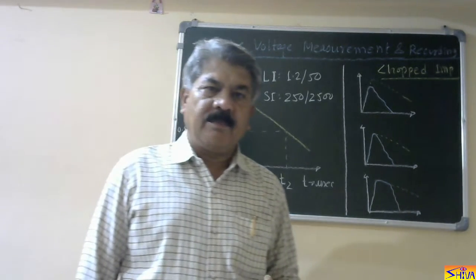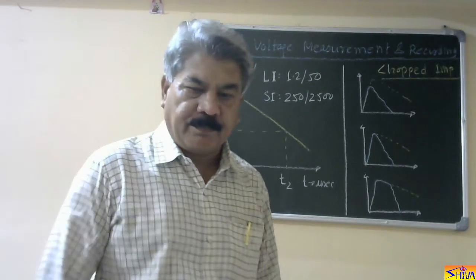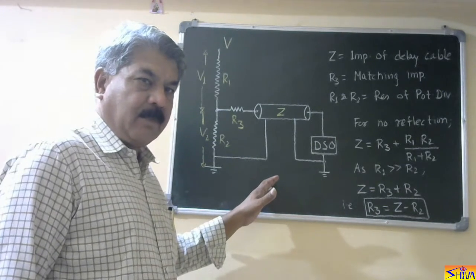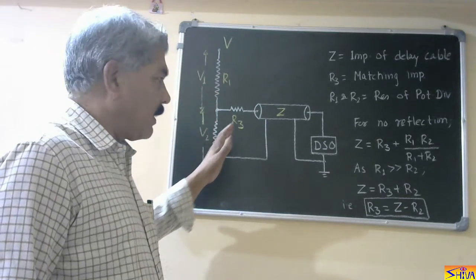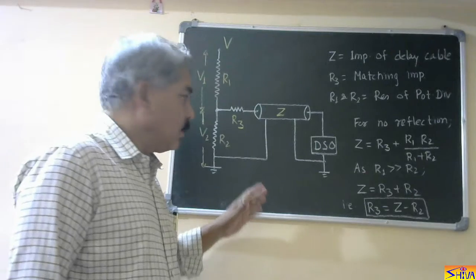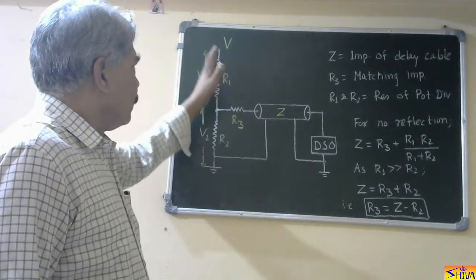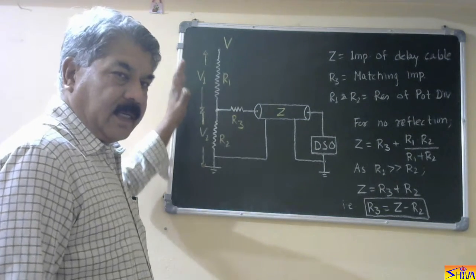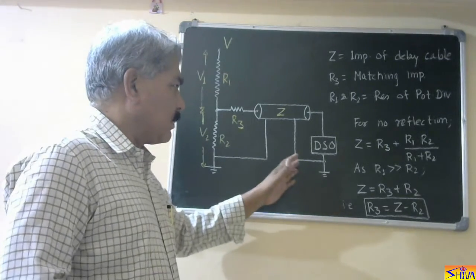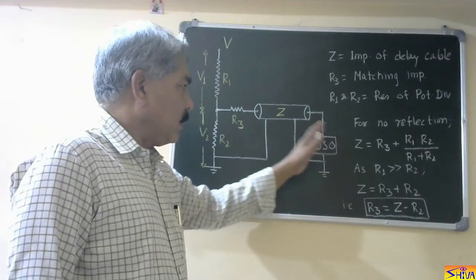So, that recording is done by potential divider plus digital storage oscilloscope. That I will explain now. This is the arrangement for impulse voltage measurement and recording. I have shown here a resistance potential divider, and for recording, a digital storage oscilloscope is there. We can use a capacitance potential divider also. The high voltage transformer, that is the impulse generator, test object, and this resistance potential divider, they all are subjected to high voltage. So, this digital storage oscilloscope is used for measurement purpose, and the control panel for this impulse generator is also near to this digital storage oscilloscope.